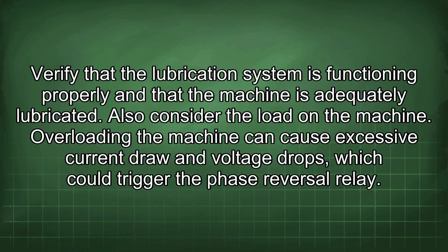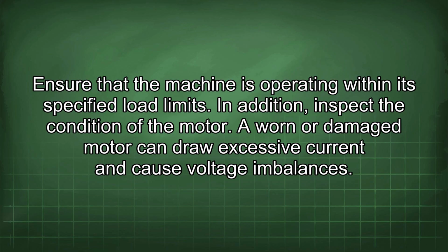Also consider the load on the machine. Overloading the machine can cause excessive current draw and voltage drops, which could trigger the phase reversal relay. Ensure that the machine is operating within its specified load limits.